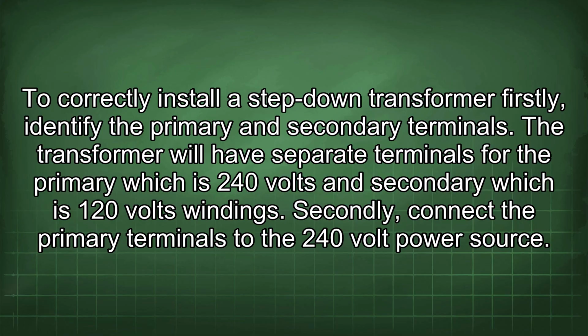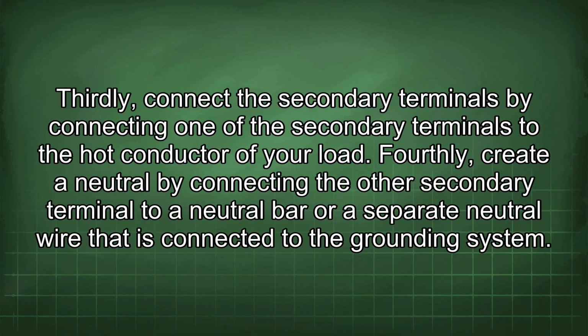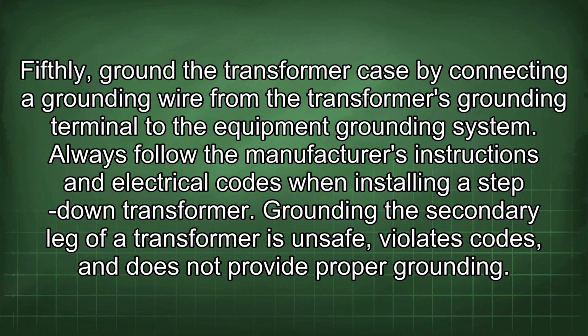Secondly, connect the primary terminals to the 240 volt power source. Thirdly, connect the secondary terminals by connecting one of the secondary terminals to the hot conductor of your load. Fourthly, create a neutral by connecting the other secondary terminal to a neutral bar or a separate neutral wire that is connected to the grounding system. Fifthly, ground the transformer case by connecting a grounding wire from the transformer's grounding terminal to the equipment grounding system.